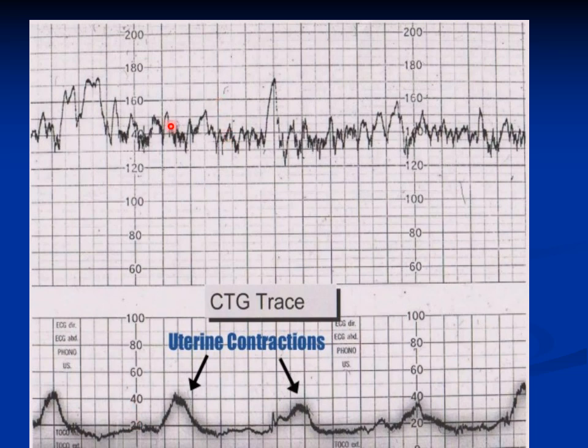Cardiotocography. This is the cardiography part, and this is the toco, which means the pressure, the tocography part. Here, this is the baseline. The rise indicates uterine contraction. Put in mind that here each one square equals 1 minute. So from this to this is 10 minutes. In these 10 minutes, we record the number of contractions. It is 1 and 2. So this is 2 contractions in 10 minutes.